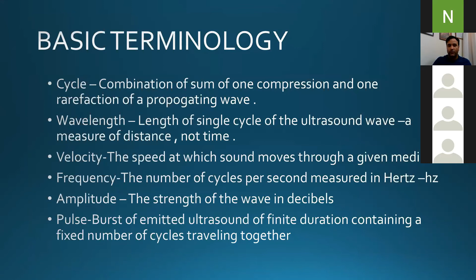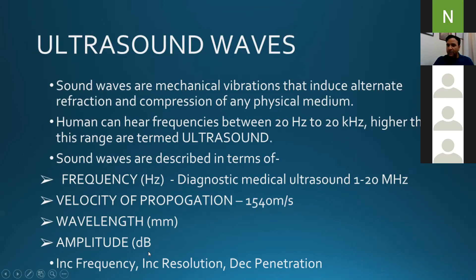So we need to know a bit about the sound waves, that is pure physics, the frequency, right? In diagnostic medical ultrasound, the frequencies that we utilize are somewhere around 1 to 20 megahertz. Velocity of propagation, the velocity of the sound, is 1540 meters per second. Wavelength is the distance between two successive waves, either two troughs or two peaks on the upper side of the horizontal or the lower side of the horizontal. Then the amplitude is in decibels. Amplitude means noise level, right? So it is in decibels.